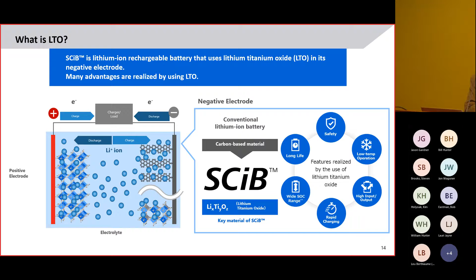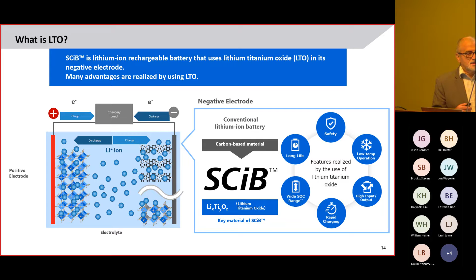Safety was the number one concern, and then it has to last a long time. One thing I want to draw your attention to: with VRLAs we get floating voltage, so we charge the battery, float it, and keep it floating, that's what they're designed for. With lithium-ion batteries, all chemistries, you remove that floating voltage or current. You bring it up to 100% state of charge, SOC, and then remove that element. That's one of the requirements within UL for all lithium-ion batteries to prevent or avoid thermal runaway, which is the main cause of failure. That's why it's done.